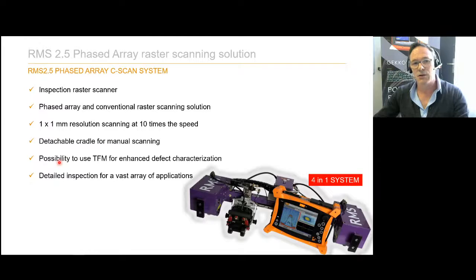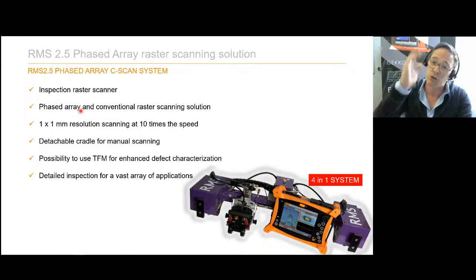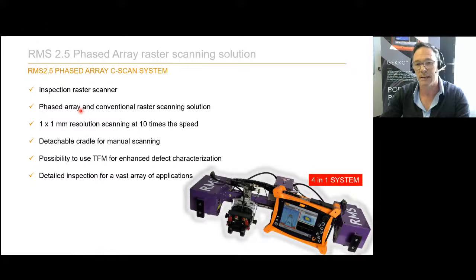If we look at the system, it's an inspection raster scanner. What we saw with the Scorpion was just one straight scan line that we're creating. Here we're scanning a complete raster and mapping out a whole area on a vessel or a tank. We're using a phased array with a conventional probe, 64 elements. We have a 1x1 millimeter resolution. And compared to normal scanning with a single probe, it's probably about 10 times faster at a very high resolution of 1x1.